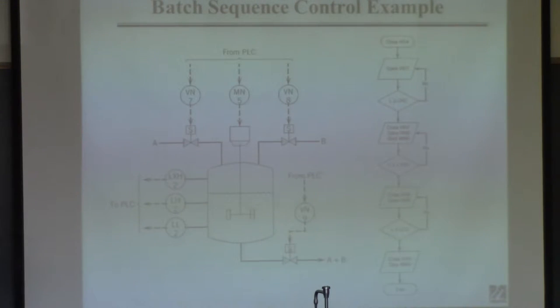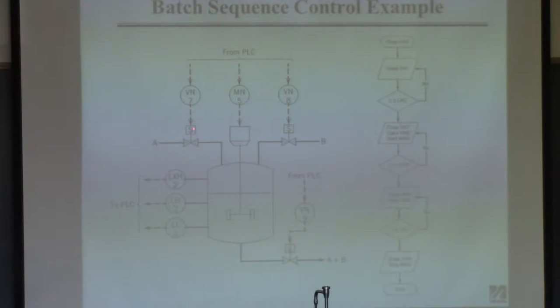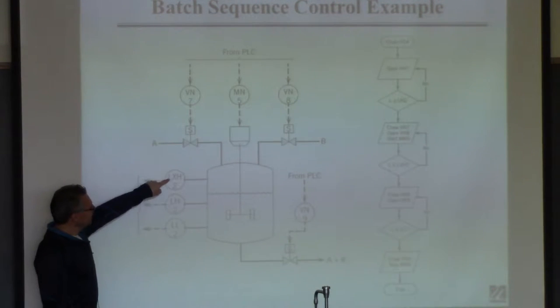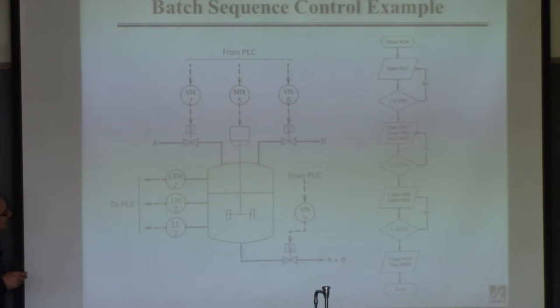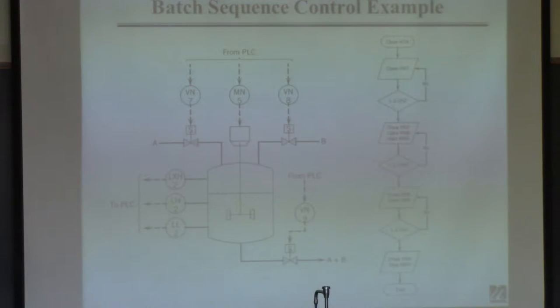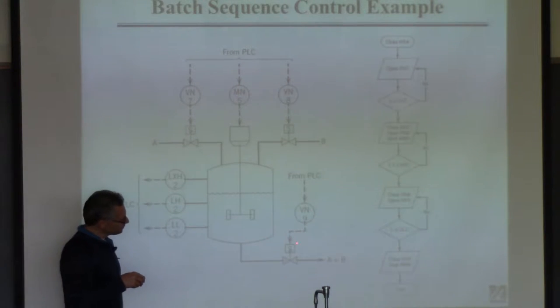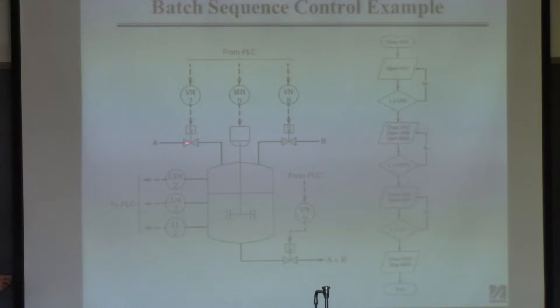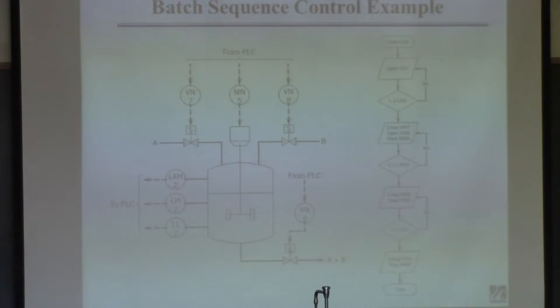Here's an example of a series of logic steps. You have a reactor with two reactants, A and B, a mixer, and three sensor measurements: level low, level high, and level extra high. You have an exit and valves called solenoids — meaning the valve is either all the way open or all the way closed. We're not worried about graded responses; we're going to open it all the way or shut it off completely.